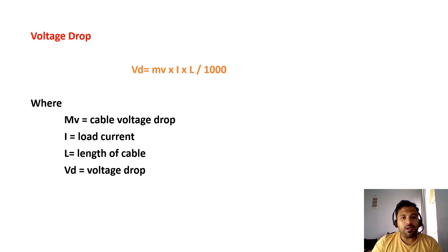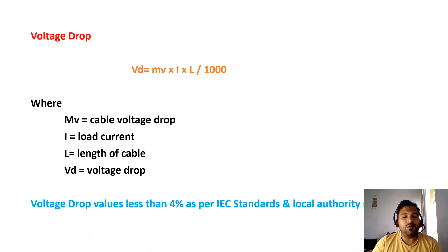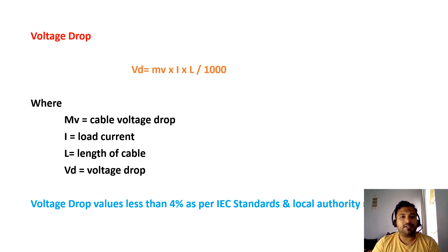I will show you an Excel sheet where we will enter the values and get the result. Before that, we have to know that the voltage drop value should be less than 4% according to IEC standards as well as local authority standards.